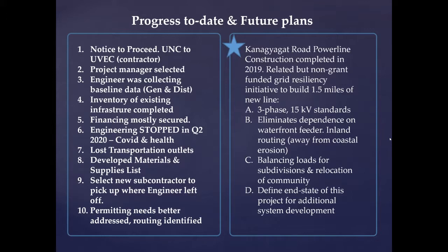What we found happening in the community was that when there was additional wind on the system, more wind turbines would spin and put out more power. When that happened, you'd normally think our diesel generation would go down. But in fact, because of the power line constraints with lower voltage, supporting the wind turbines caused a voltage drop, as Reese was talking about.